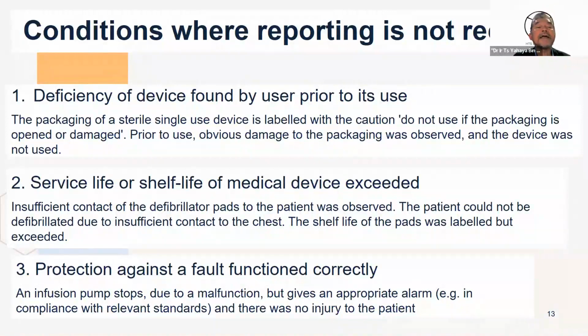Secondly, if the service life or the shelf life of the medical device is exceeded. We see this is quite normal. There is an expiry date. An example is insufficient contact of the defib pad to the patient who was observed. The patient could not be defibrillated due to insufficient contact to the chest. So there was no contact by the defib pad on the patient's chest. So there's no need to report, because the shelf life of the pad was labeled, and although the shelf life has been exceeded, it has never been in contact with the patient. So there's no need for it to be reported, okay?